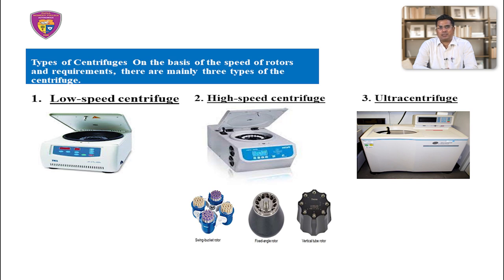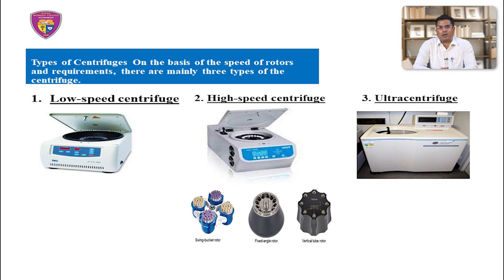The second type is the high-speed centrifuge, which has high-speed rotors and is used in more sophisticated biochemical applications. It has a temperature control mechanism in the rotor chamber, as most biochemicals have optimal thermal requirements. Its maximum speed is 15,000 to 20,000 RPM. It generally has three types of rotors: fixed angle, swinging bucket, and vertical rotors. Speed and temperature required for sensitive biological samples can be controlled. A diagram is shown in this slide.